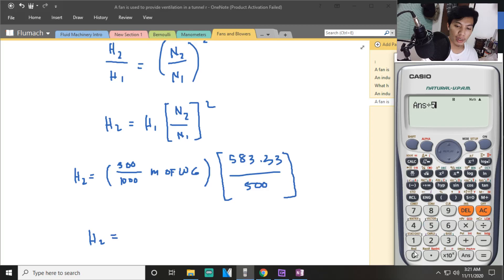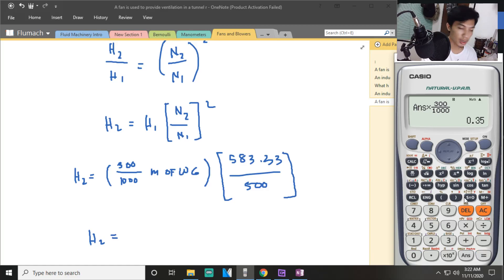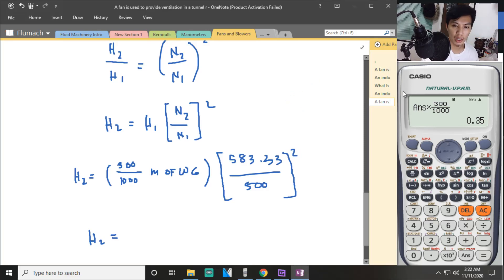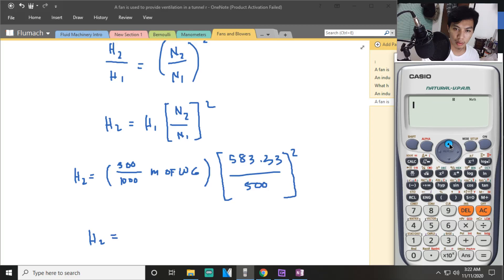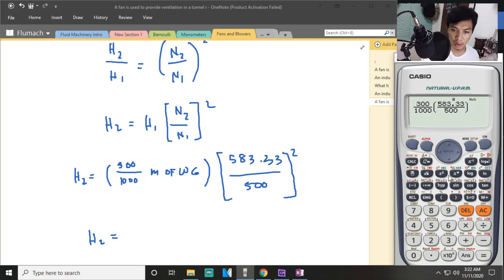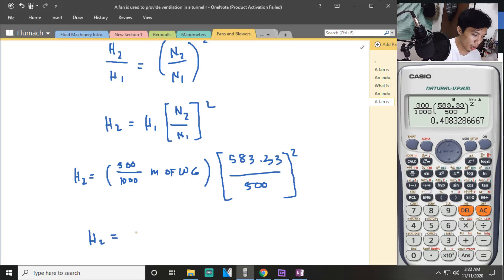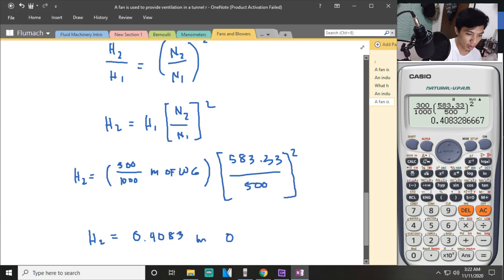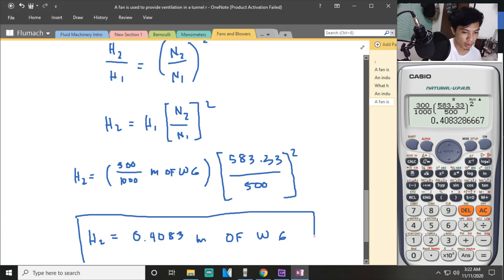Computing the result: (300 divided by 1000) multiplied by (583.33 divided by 500) squared. The answer is 0.4083 meters of water, which is approximately 408.3 millimeters of water. That is how you solve this problem using the fan affinity laws.